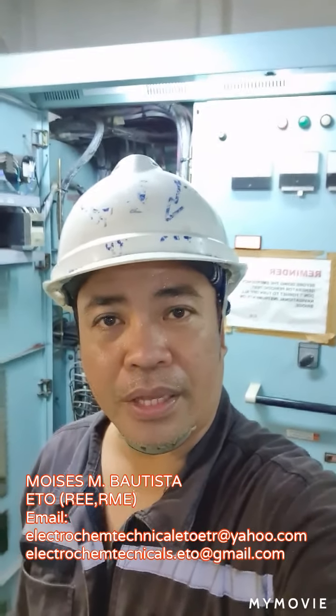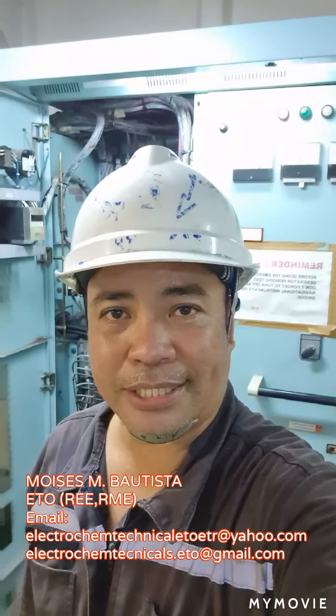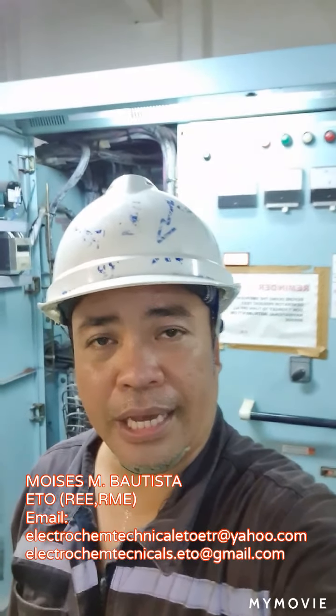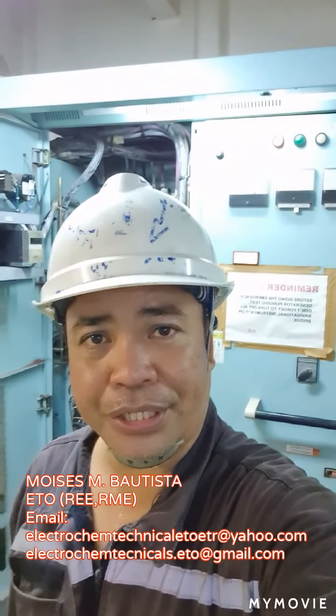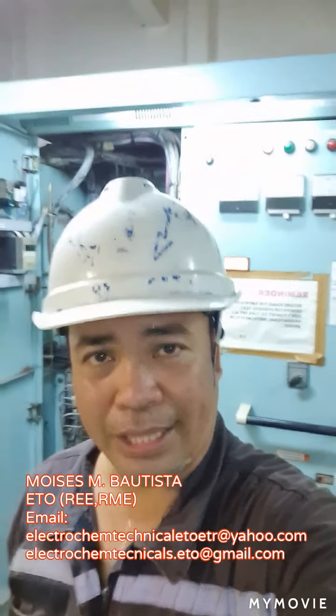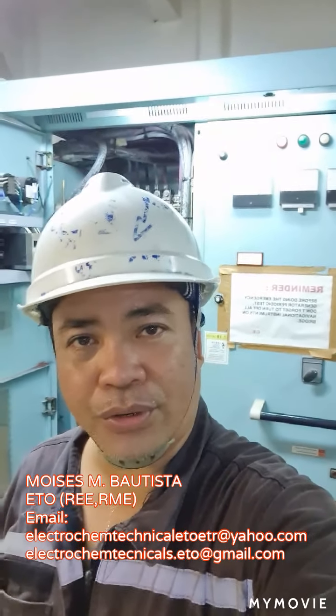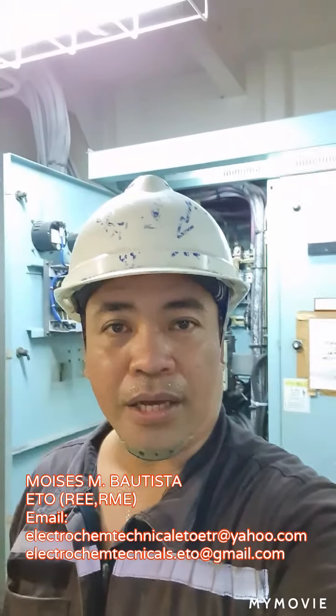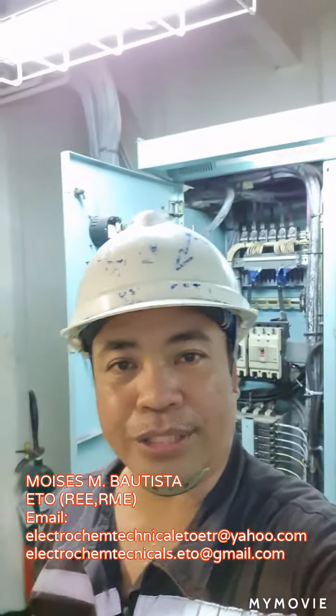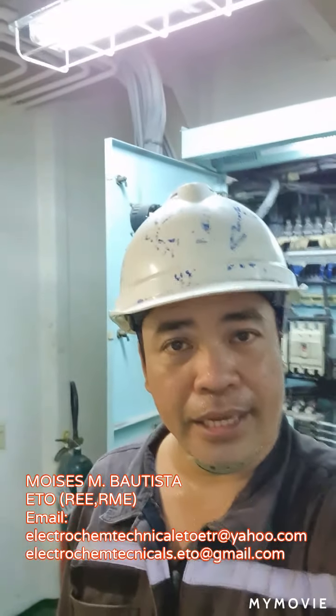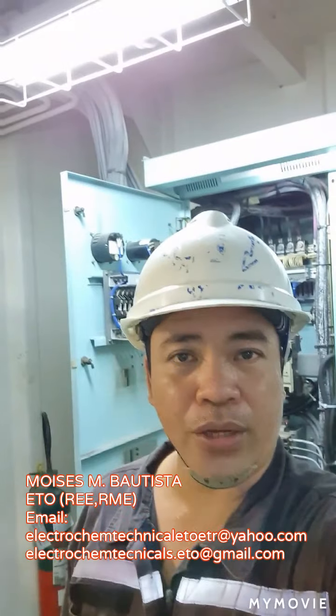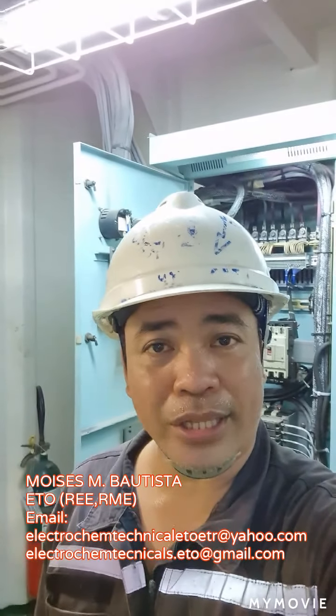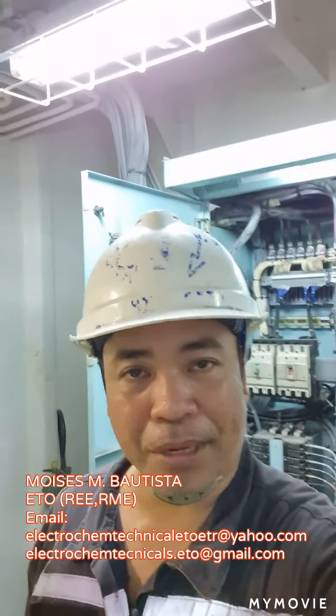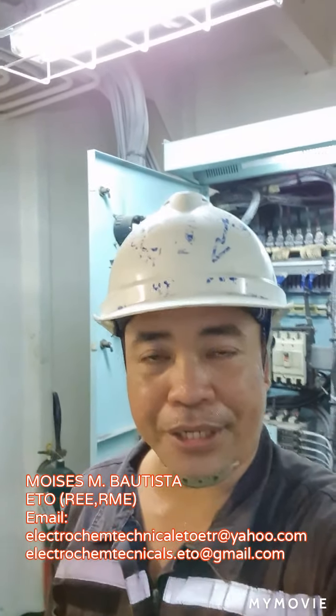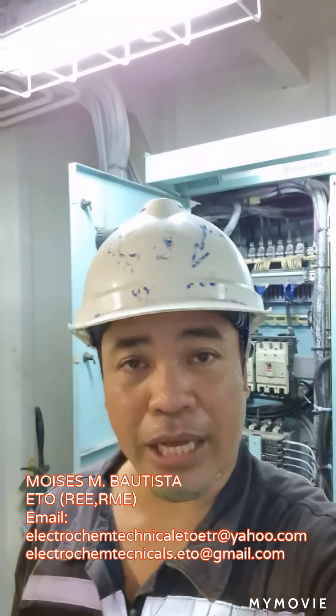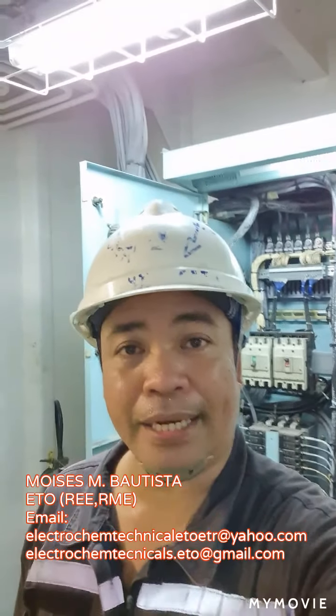When the power is less than 50 kilowatts, just switch off and disengage the air circuit breaker of the generator and let it cool down. Then the generator must be stopped. Once the circuit breaker on the shore connection box is switched on, you will automatically feed that voltage from shore to the bus bar. And this bus bar is directly connected to the main switchboard panel.